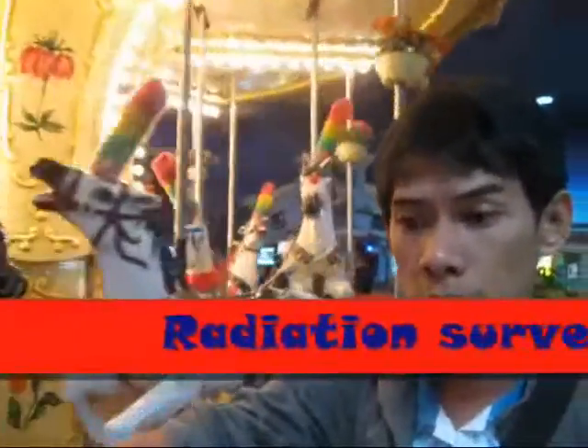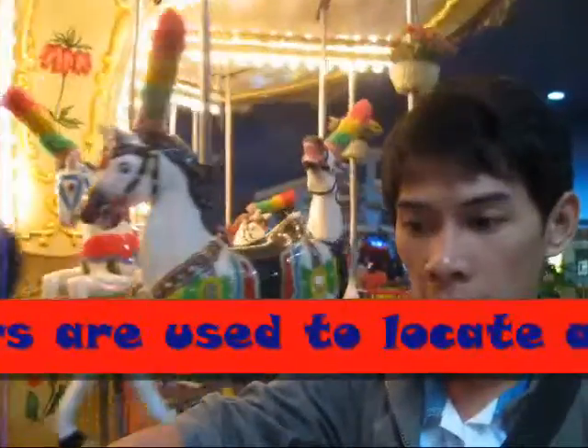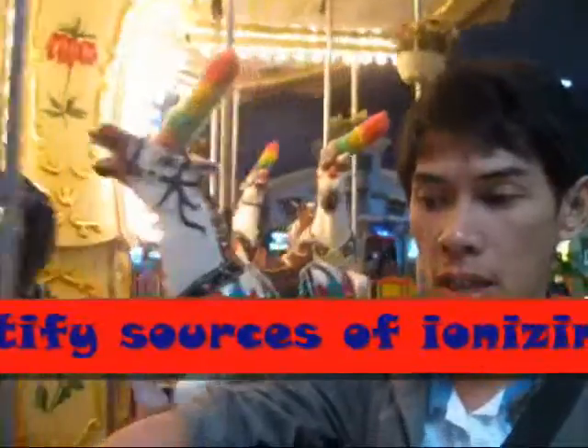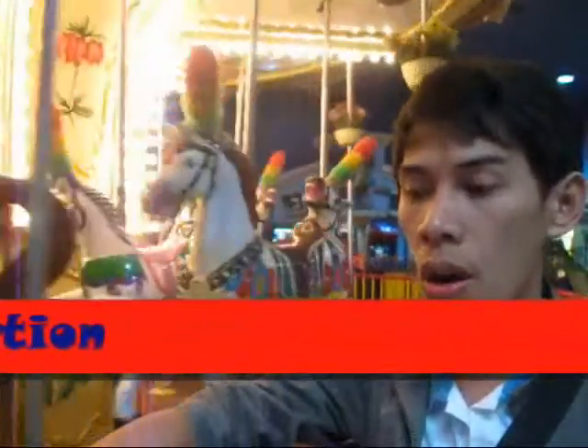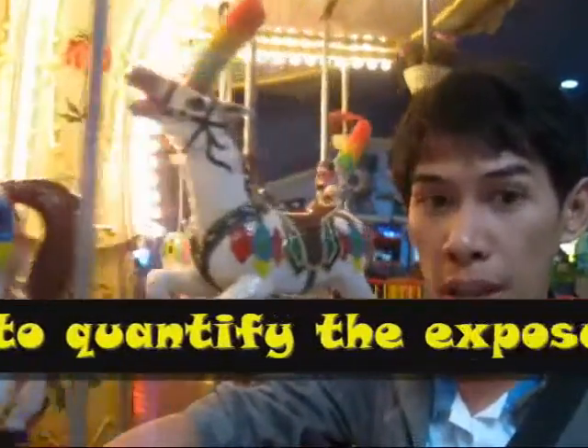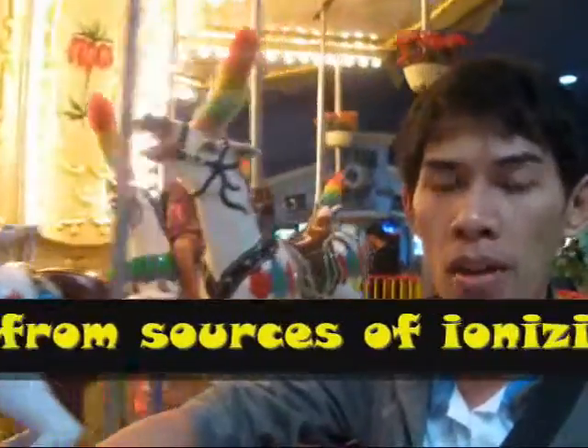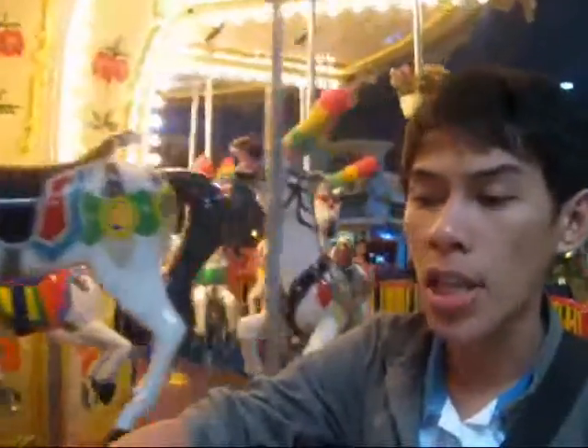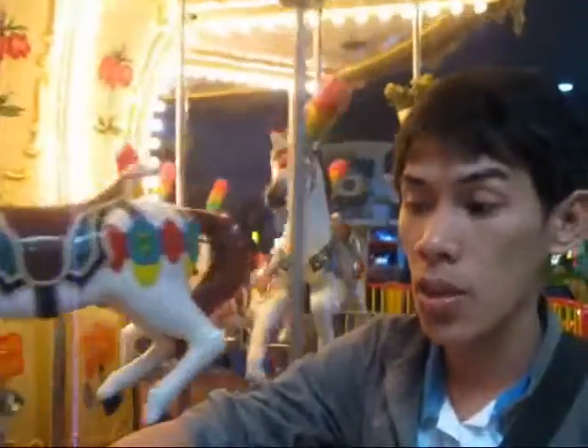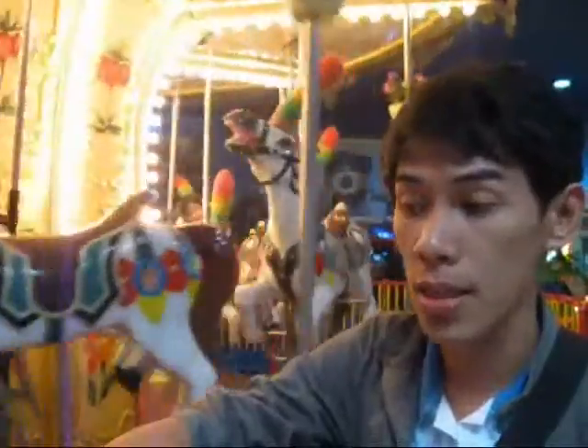Radiation survey meters are used to locate and quantify sources of ionizing radiation, or to quantify the exposure rate from sources of ionizing radiation, to assess the quantity of radioactive materials present. Survey meters are typically calibrated to measure counts per unit time, or to measure the exposure rate from radiation sources.